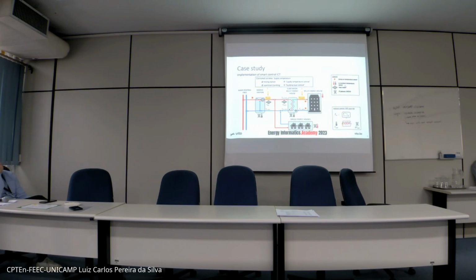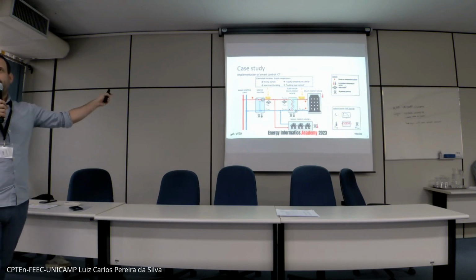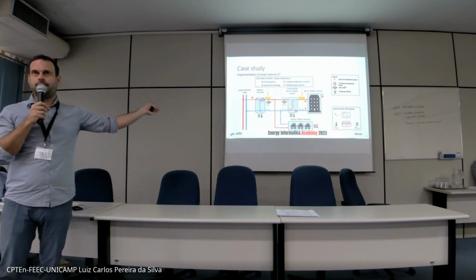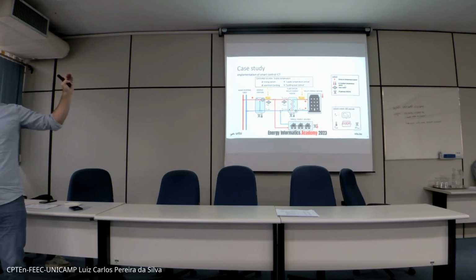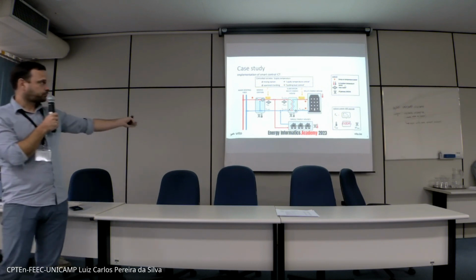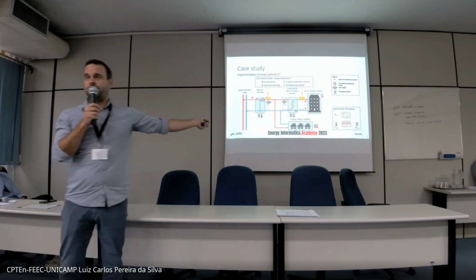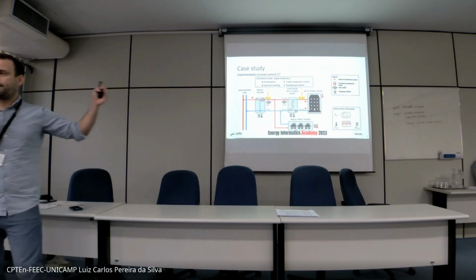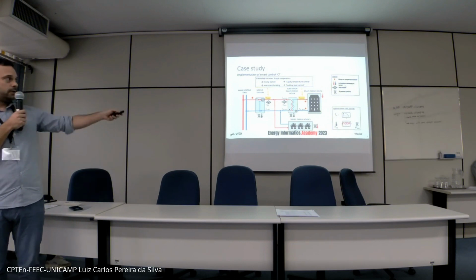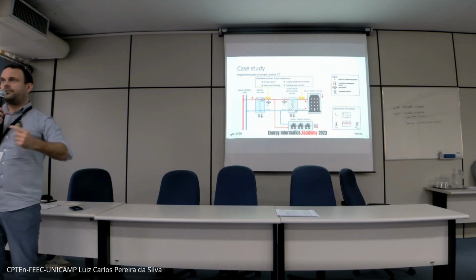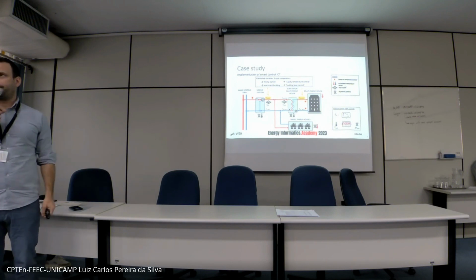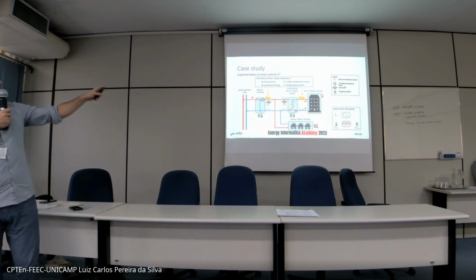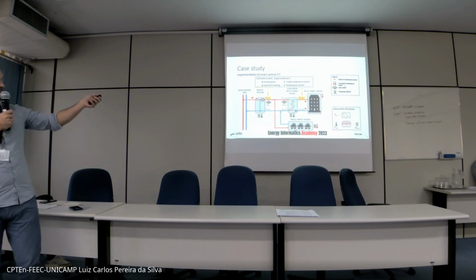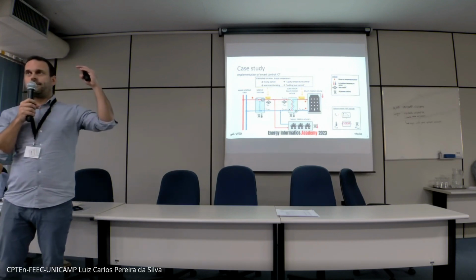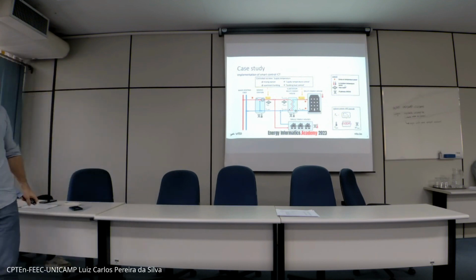Here you see the schematics of what we did. So you have the main heating grid, which is operated by EI.A at high temperature. In peak winter conditions, it's, I think, a supply temperature of 130 degrees. But by installing this mixing station, you can reduce the supply temperature going into the network branch itself by mixing return with the hot supply temperature. So that's at this point 1 there.